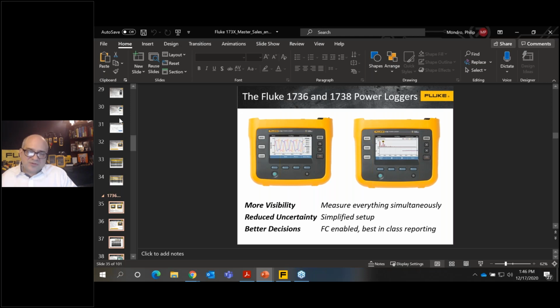instead of 480, you're dropping me down to 430 on a particular phase, or you're single phasing me, which means a press happened to trip and I can't get it restarted because I'm imbalanced. I've got a neighbor that has very specific, they're a battery manufacturer or whatever they do, crazy manufacturing. They're next door, and based on however they're using electricity, it's generating a transient or harmonics, and I'm on the same wires out front.